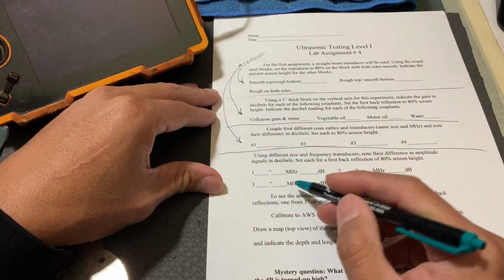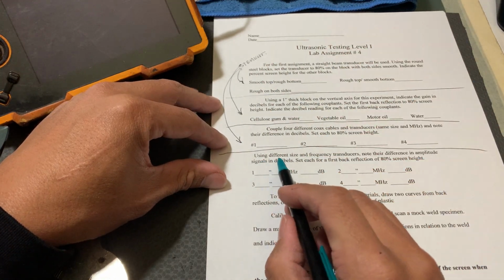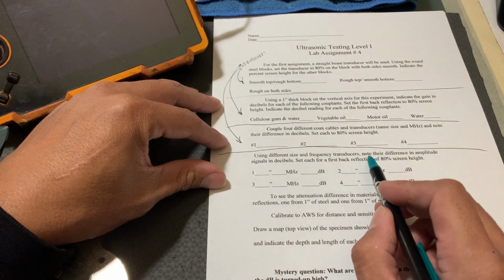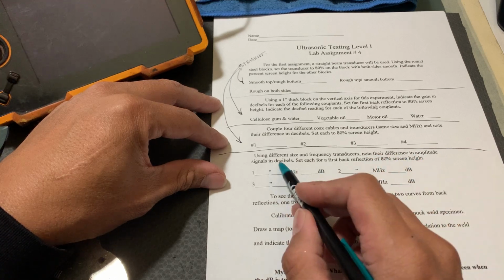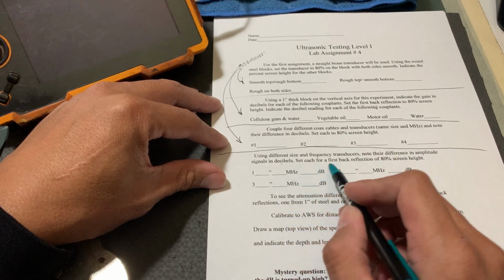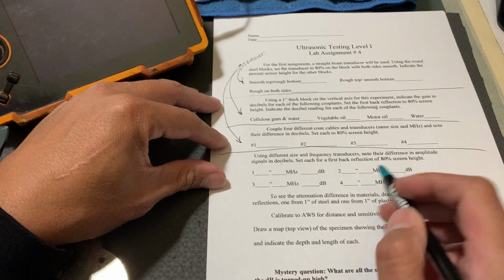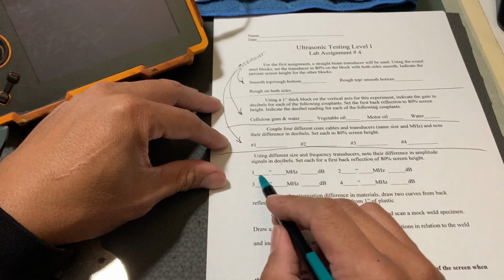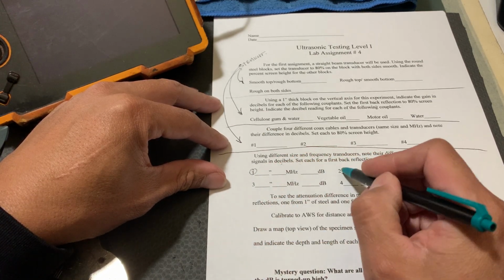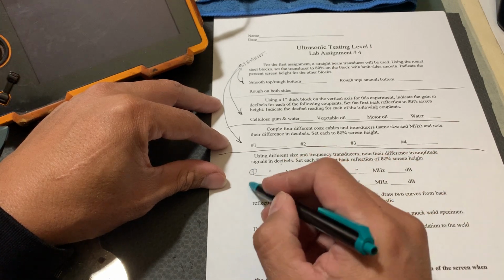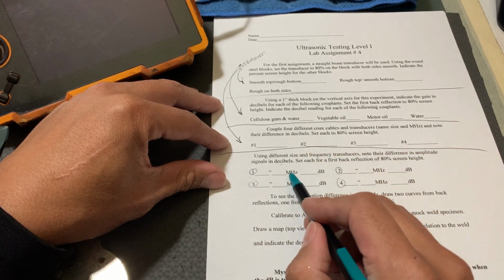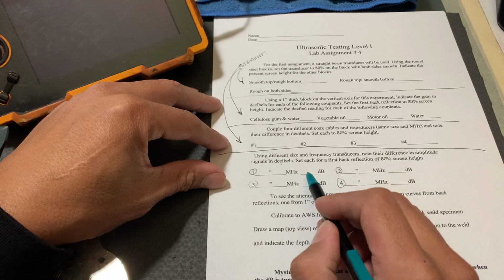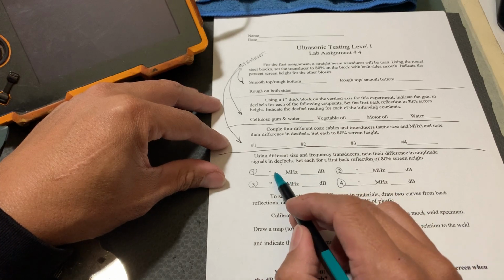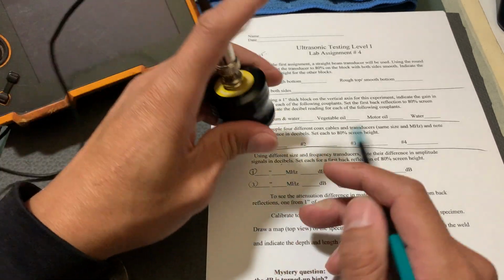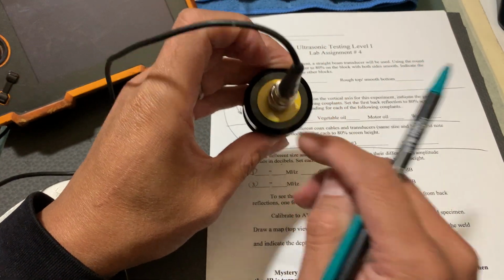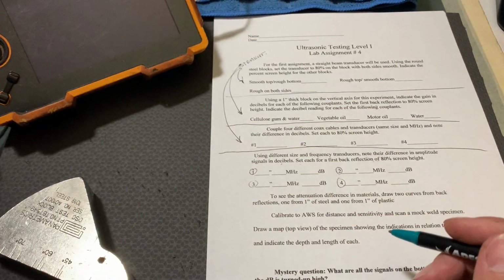So that's the fourth activity. The fifth activity is using different size and frequency transducers. Note their difference in amplitude, signal, and decibels. Set each of the first back reflection to 80% screen height. So we're going to get different transducers. So you got 4 different types. 1, 2, 3, 4. You're going to note the decibel on here of what it reads, and you're going to note the megahertz reading. You can find the megahertz reading on the information on transducers there, and we'll get to that in a bit.